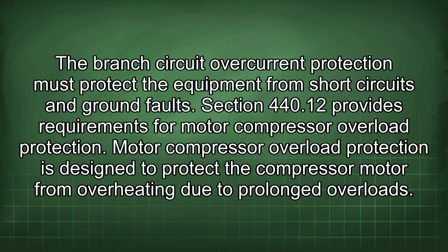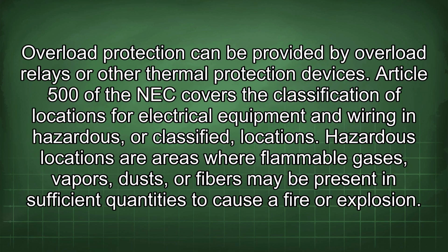Section 440.12 provides requirements for motor compressor overload protection. Motor compressor overload protection is designed to protect the compressor motor from overheating due to prolonged overloads. Overload protection can be provided by overload relays or other thermal protection devices.